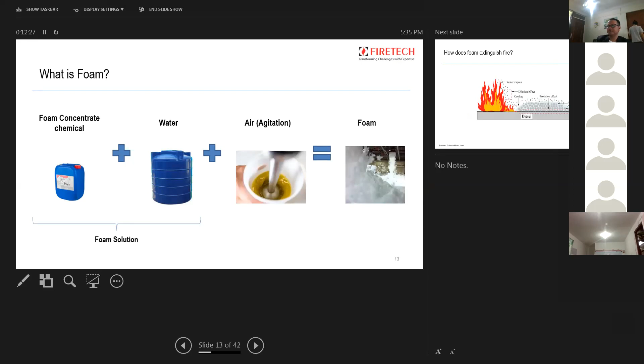Now, how does foam extinguish a fire? Let's say this is diesel fuel. When the foam is introduced to the diesel fuel, you notice there is a foam layer - an aqueous film that forms a blanket. There is an isolation effect between the oxygen outside and the fuel inside. That's why, if you remember the basics of fire from earlier, the oxygen has been eliminated, so fire will not happen.